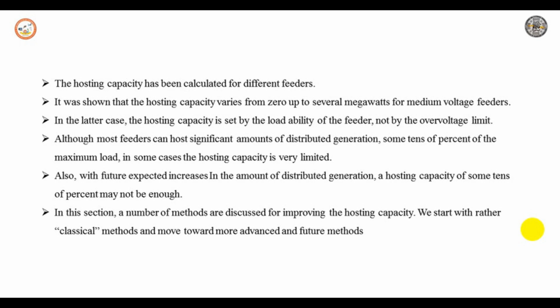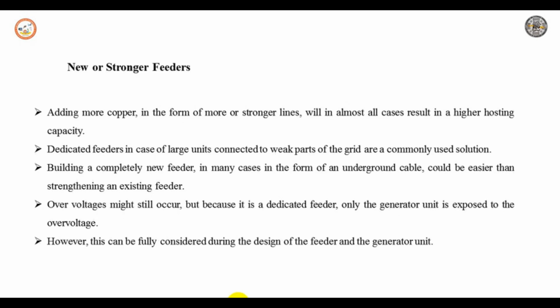Among them, the first one is a new or stronger feeder. Adding more copper in the form of more or stronger lines will in almost all cases result in higher hosting capacity. A dedicated feeder, in the case of a large unit connected to a weaker part of the grid, is commonly used as a solution. Building a completely new feeder, in many cases in the form of underground cable, could be easier than strengthening the existing feeder. Over voltage might still occur, but because it is a dedicated feeder, only the generator unit is exposed to the over voltage. However, this can be fully considered during the design of the feeder and the generator unit.